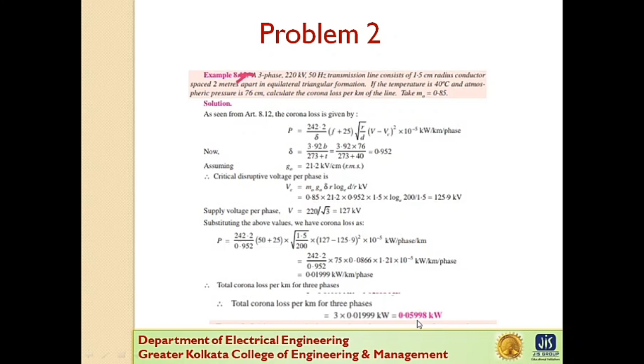By putting the value of V and Vc, the radius 1.5 centimeter, and the small d, the spacing between conductors, 2 meters, that means 200 centimeters, we get P equal to 0.01999 kilowatt per kilometer per phase. But we have to calculate corona loss per kilometer of the line. For single phase, the power loss is 0.01999 kilowatt per kilometer. For 3 phase, we multiply this figure by 3 and the value is 0.05998 kilowatt. So the total corona loss per kilometer for 3 phase is 0.05998 kilowatt.